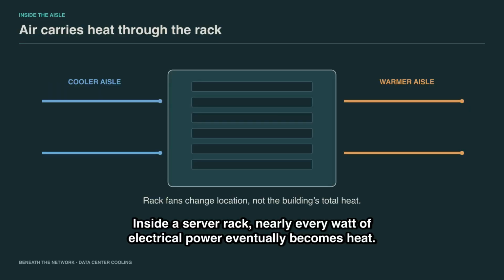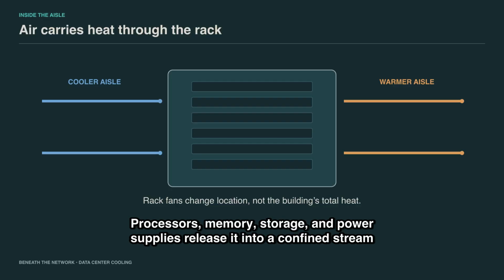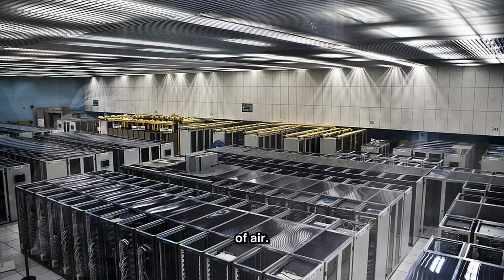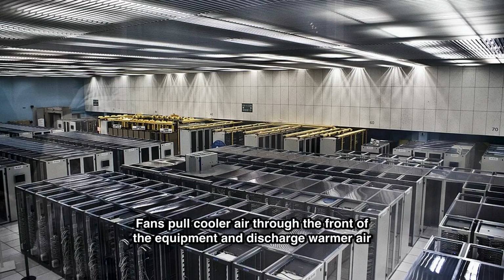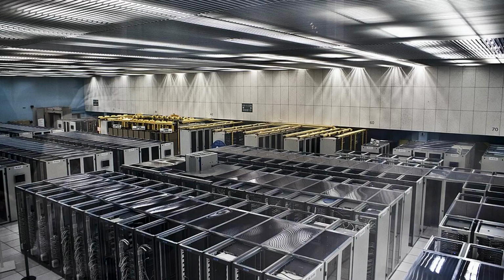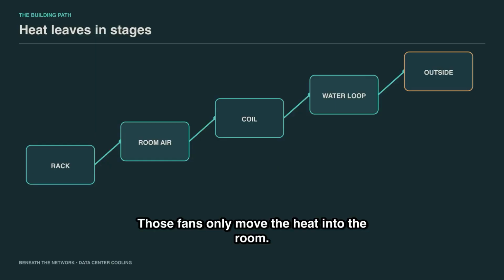Inside a server rack, nearly every watt of electrical power eventually becomes heat. Processors, memory, storage, and power supplies release it into a confined stream of air. Fans pull cooler air through the front of the equipment and discharge warmer air behind it. Those fans only move the heat into the room.